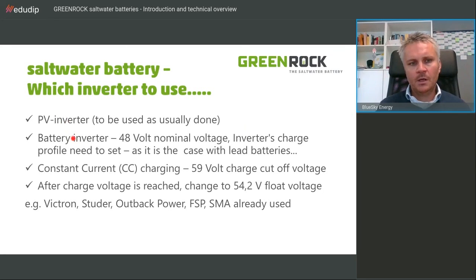On the battery inverter side, we want to have battery inverters which are on 48 volt nominal, and the inverter's charge profile needs to be set, as I will show afterwards. In most cases, you are using a lead battery charging, discharging profile and doing the settings accordingly. And there is a question, is there any compatibility with Studer? As long as Studer has got a 48 volt battery version, yes. And we did already projects with Studer. So from that end, I think Studer is one of those battery inverters which are a good fit for our batteries, and we executed projects with that already.